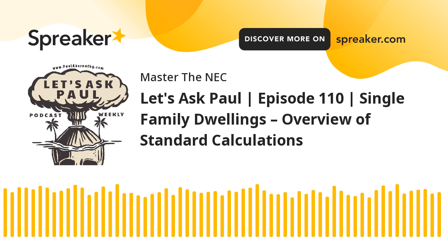So we would go to table 310.16, okay? And remember, I didn't give you any adjustment or corrections. We're just talking amps. I'm going to be in the 75-degree column, and we're going to assume copper unless stated otherwise. The reason we're going to be in the 75-degree column is because of the terminal limitations in 110.14(C)(1). And that means that it is over 100 amps, so it's going to be under the 75.